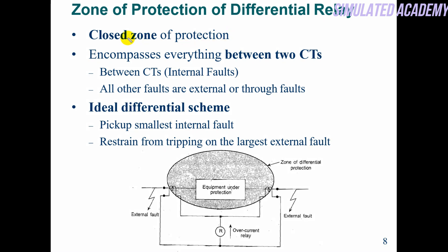Zone of protection for differential relay — close zone of protection. Zone of protection is the area where CTs and PTs are placed, i.e., the external boundary defined by the CT/PT locations, and the equipment inside that zone is what we protect. It is the area between the CTs. Any fault outside this zone is called a through fault, and any fault inside is called an internal fault. An ideal differential scheme operates for minimum internal fault and restrains for any external fault.